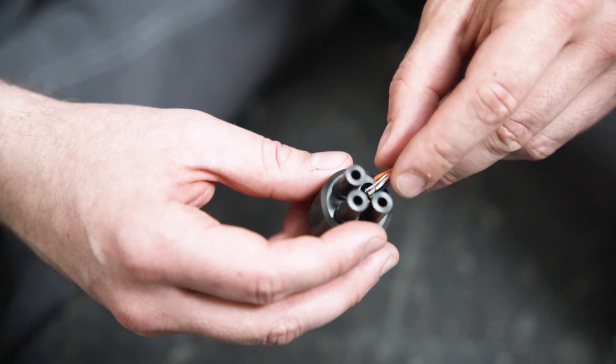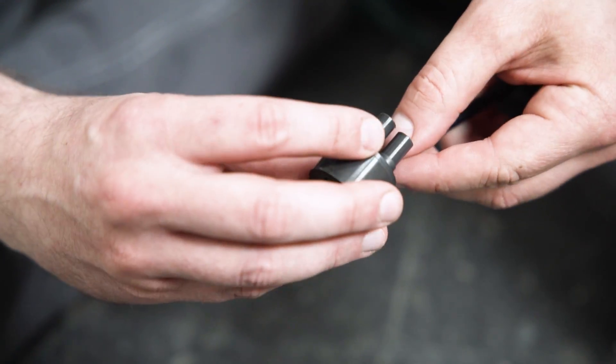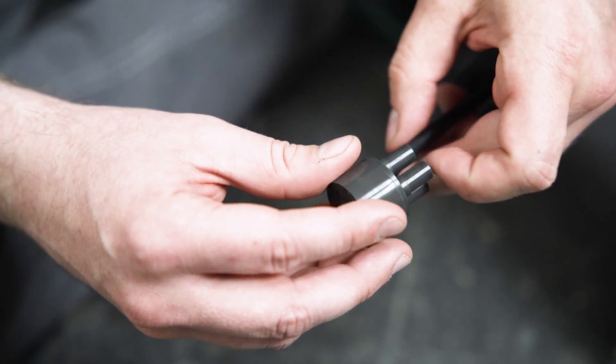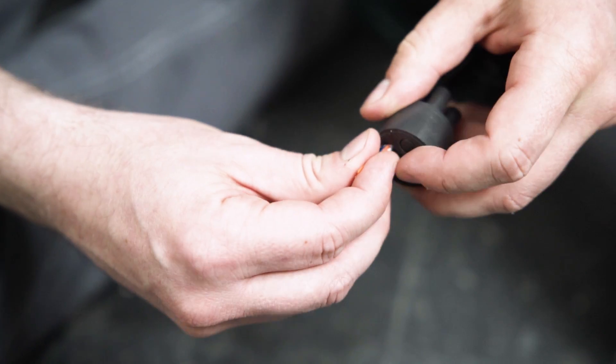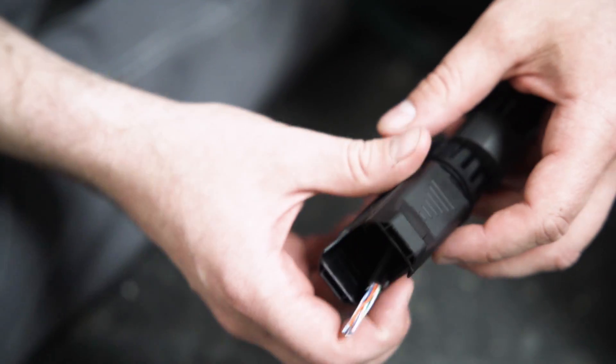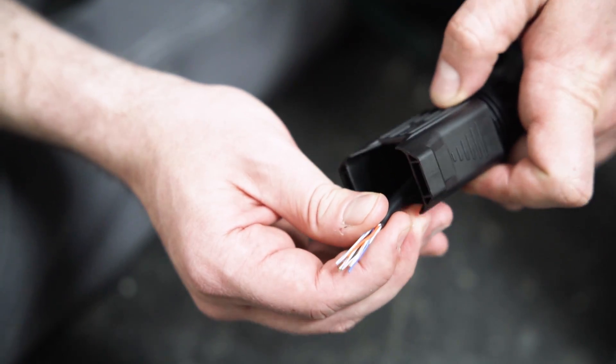Remove approximately four to five centimeters of the cable sheath of the communication cables. Then strip approximately five to seven millimeters off the inner cables. Fit the cables with end sleeves before you push them into the plug.